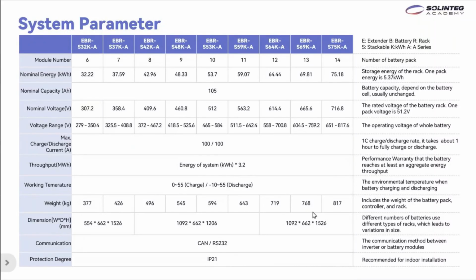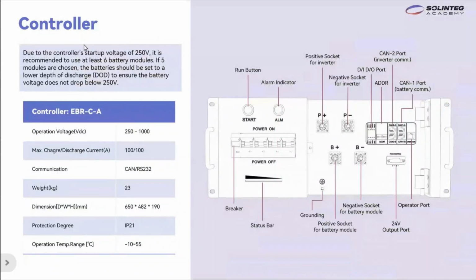Next, about the parameters of the controller. The operation voltage of the controller is 250 to 1000 volts. This is why we suggest the system be used with 6 pieces, because you can see the 250 volt requirement. The user can also use 5 pieces, since one piece is 51.2 volts, so 5 pieces gives a nominal voltage of about 255.